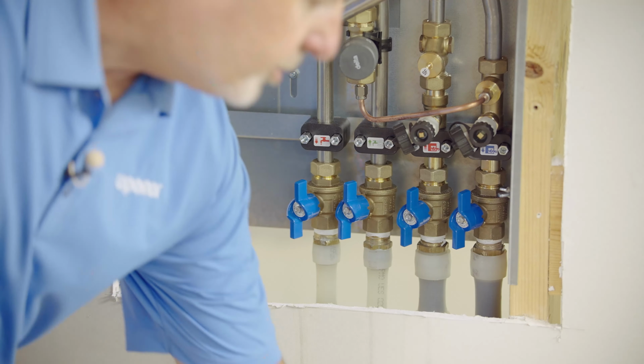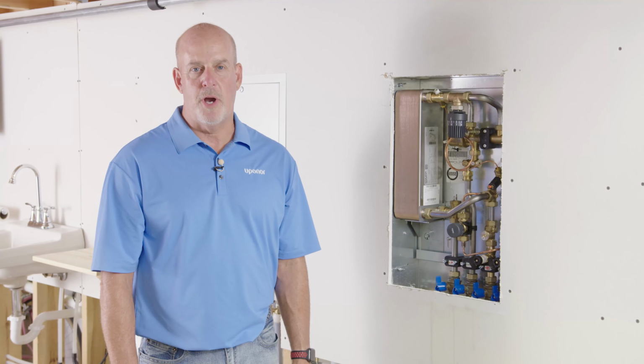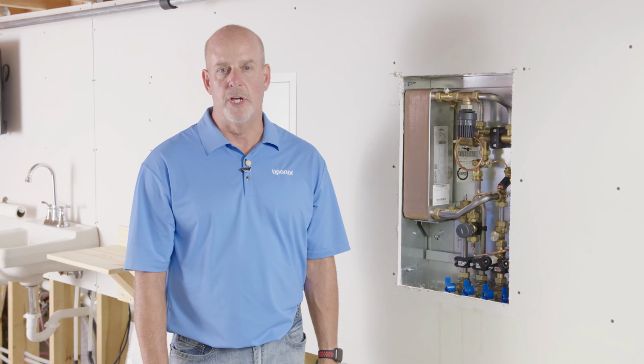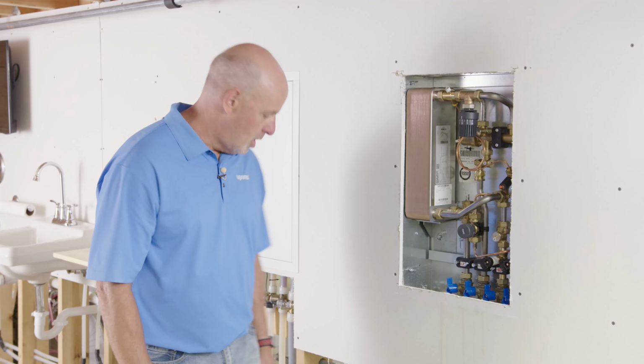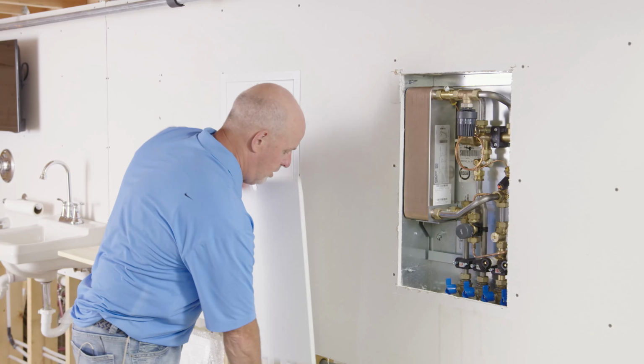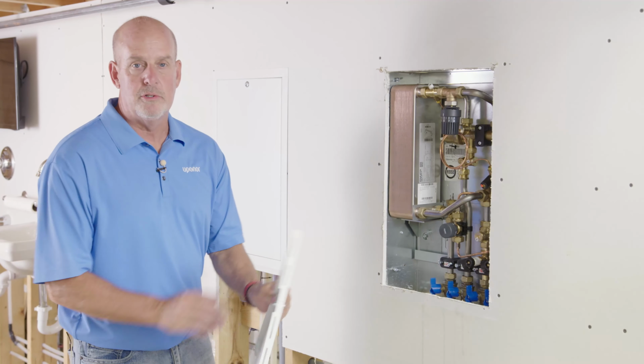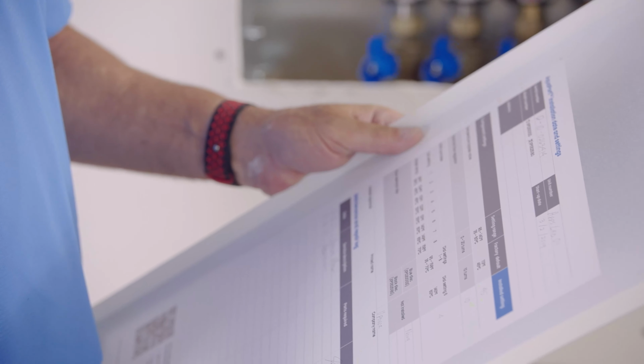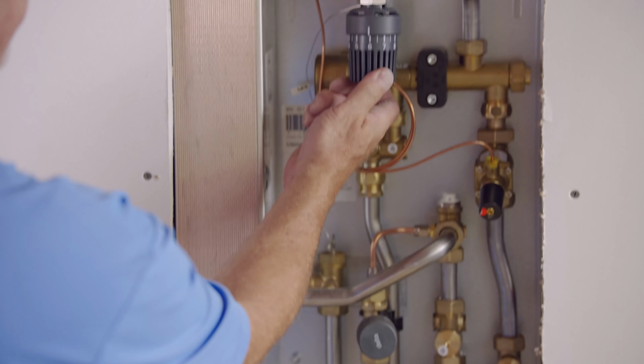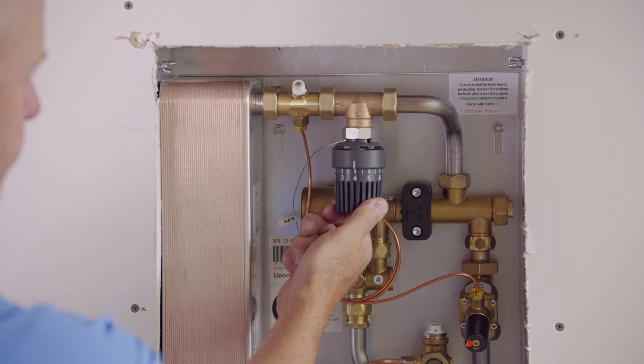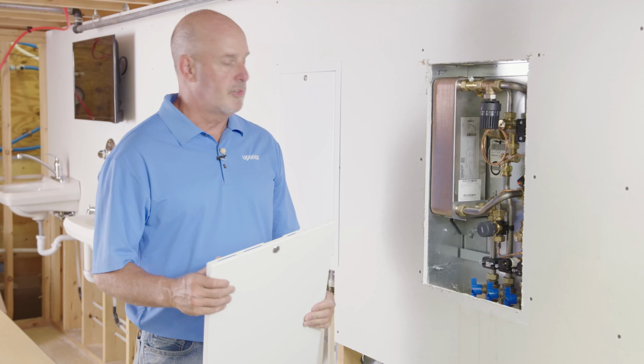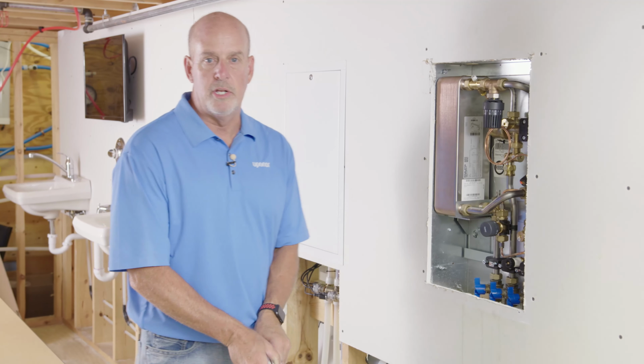Now that we've refilled the AquaPort panel and completed the purge process, we're ready to install the trim ring in the door. However, before we do, we want to transfer the settings from the old installation to the new one. In looking at the back panel, it appears the only setting that we need to adjust is for the domestic hot water temperature. It needs to be returned to a setting 4. That's the only adjustment we need to make. Now we're ready to install the trim ring.